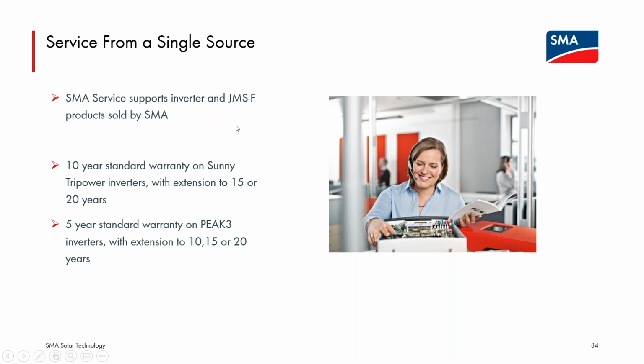But I will close. I know we're wrapping up on time, so I don't want to run over. In terms of standard warranty, the PEAK3 is in our utility scale portfolio, so the standard warranty for that is similar to our Sunny Centrals. It's a 5-year standard. The CORE1 starts at a 10-year. Both of those lines can be extended in 5-year blocks from the standard amount up to 20 years maximum. So it is possible to purchase that warranty extension at the time of purchase of the inverter, or really at any time through the factory warranty of the device.